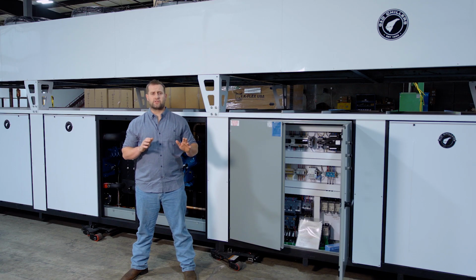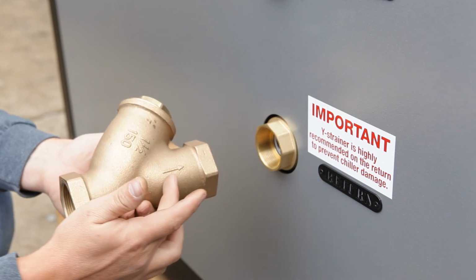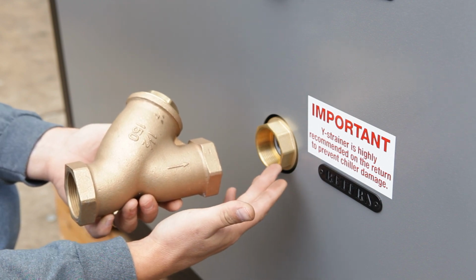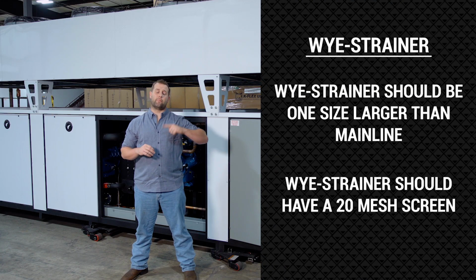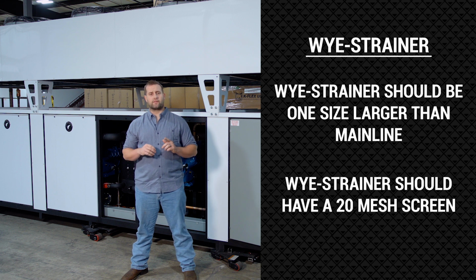So the next step, step 3 on this startup sheet, talks about a Y strainer. Exterior to the chiller, you're going to want a Y strainer on your return line right before the chiller. You want to size it one size above whatever your main process line is. The function of the Y strainer is to filter out any particulates from your process so they can't get back to the chiller. There's going to be a mesh screen in that Y strainer, and you're going to want a 20 mesh screen.